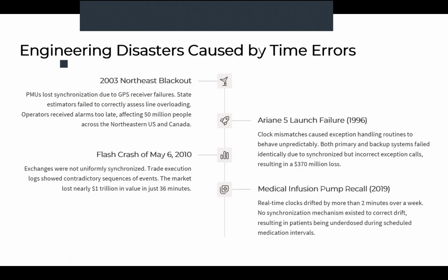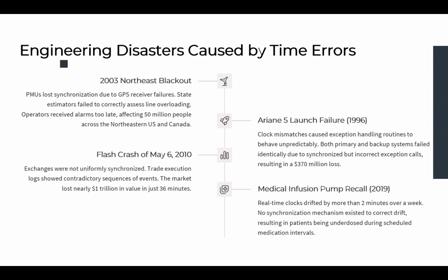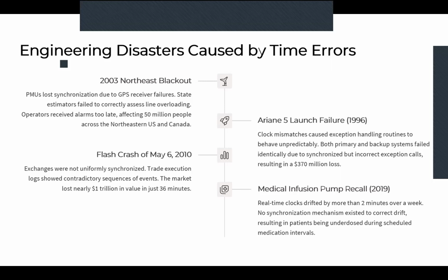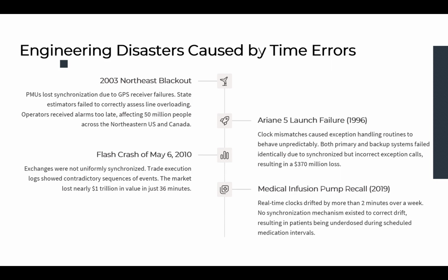in our system. Now, let's talk about some of the examples, some of the disasters that happened because of these time errors, because of the desynchronization of those clocks and times. Now, the first example is the Northeast power system blackout in 2003, which basically affected 50 million people across the northeastern US and part of Canada. It was caused because of the phasor measurement unit synchronization, because the GPS signal was lost. So when we talk about the PMU, or phasor measurement unit, PMUs require microsecond level synchronization so they can detect the phase angles of voltage or current across multiple grid nodes in the power grid.